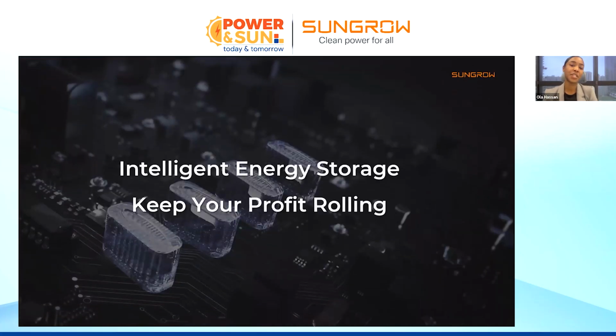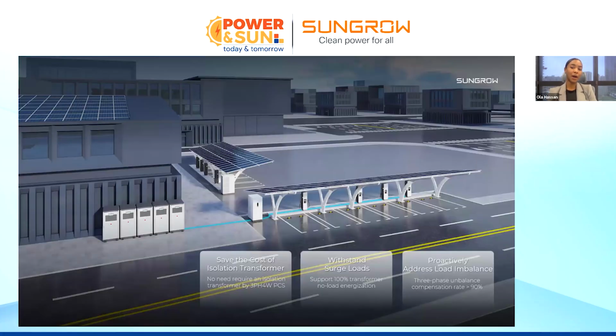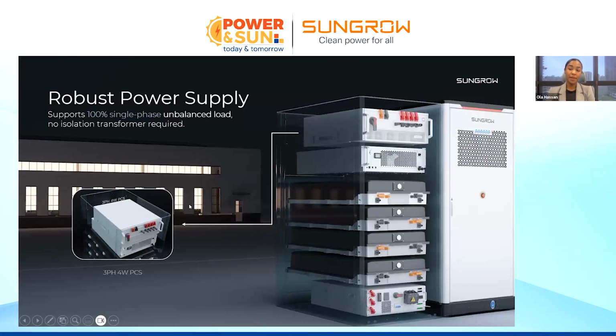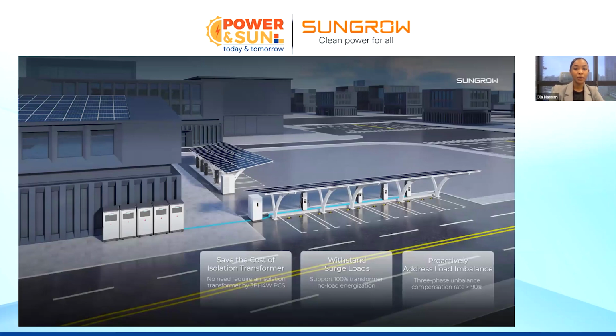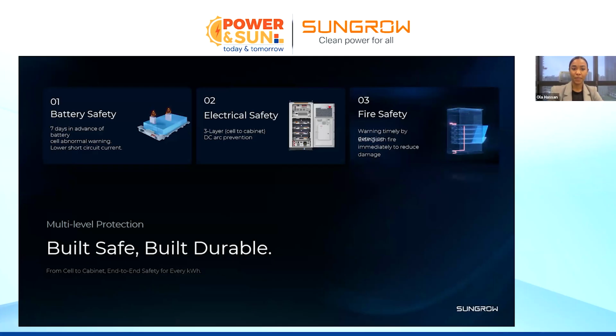All right, intelligent energy storage, keep your profit rolling. So now we're talking about how the C&I BESS systems, the latest innovation, can also reduce our capex cost. Compared to our previous series, which was three-phase, three-wire systems, there used to be an isolation transformer in case of on-grid, off-grid application. But now this is upgraded to three-phase, four-wire system. So there is a neutral cable here as well to be connected. We are eliminating the requirement for an isolation transformer, therefore reducing the capex cost initially. And also, as I mentioned, it withstands high surge current loads and also addresses the load imbalance between the three phases. So it's very durable.